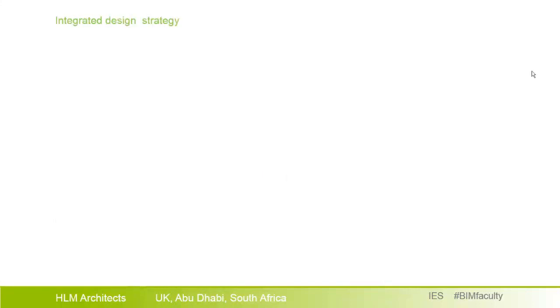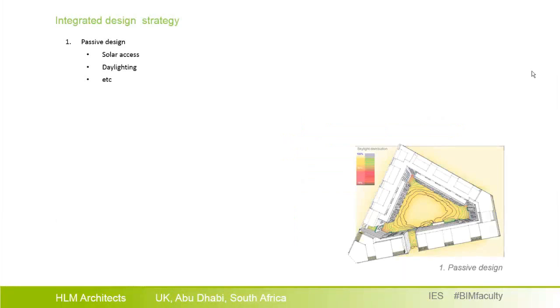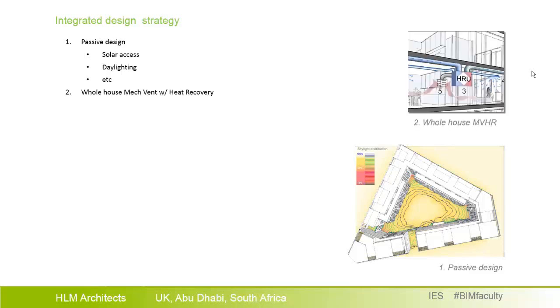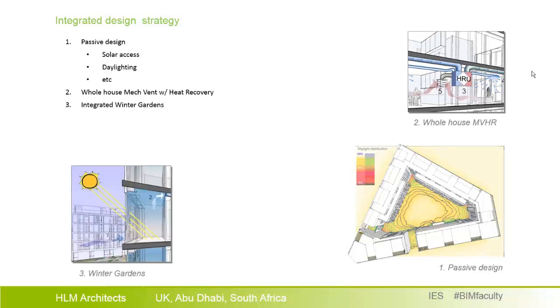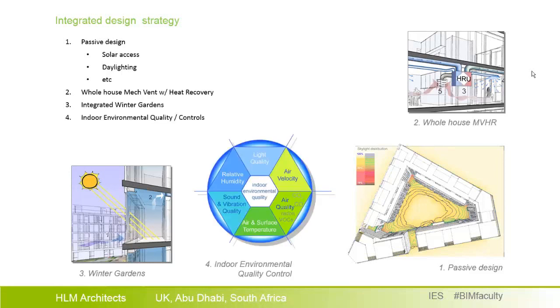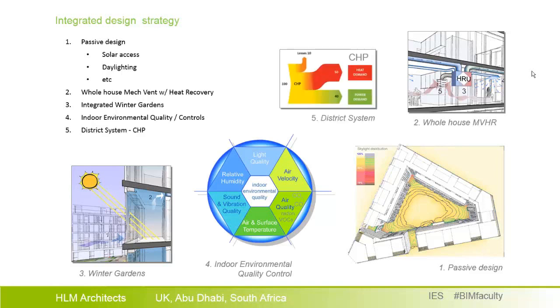The integrated design strategy is based first on a passive design strategy, including solar access distribution, daylighting, overshadowing control, interaction with the surrounding environment, and so on. Then we added whole house mechanical ventilation with heat recovery in every unit. Most units are equipped with a sun space — a winter garden — which provides additional amenity space and benefits in terms of thermal and energy control. These systems are connected and controlled on the basis of indoor environmental quality aspects, and finally the whole development is supplied by a community system fueled by a CHP.